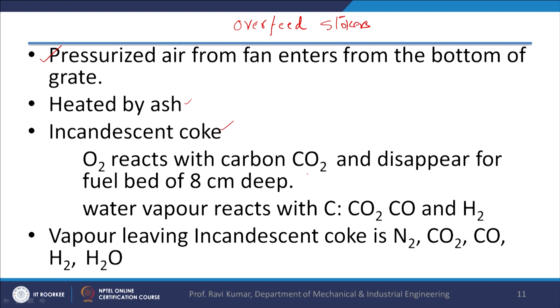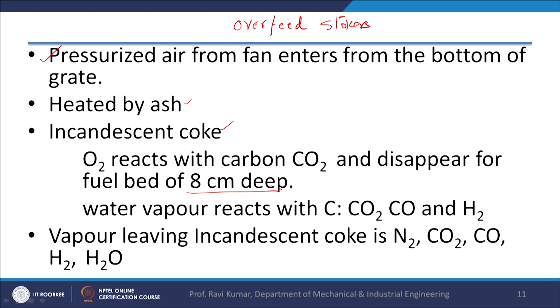The air is heated by ash. There is incandescent coke over the layer of the ash. So, oxygen reacts with the carbon to form carbon dioxide, in a fuel bed about 8 centimeters deep. Water vapor also reacts with the carbon, and they form carbon dioxide, carbon monoxide, and hydrogen is also liberated. Raw coal, as I mentioned earlier, is continuously supplied on the surface of the bed. Volatile matter distillation takes place when the hot air enters from the bottom.